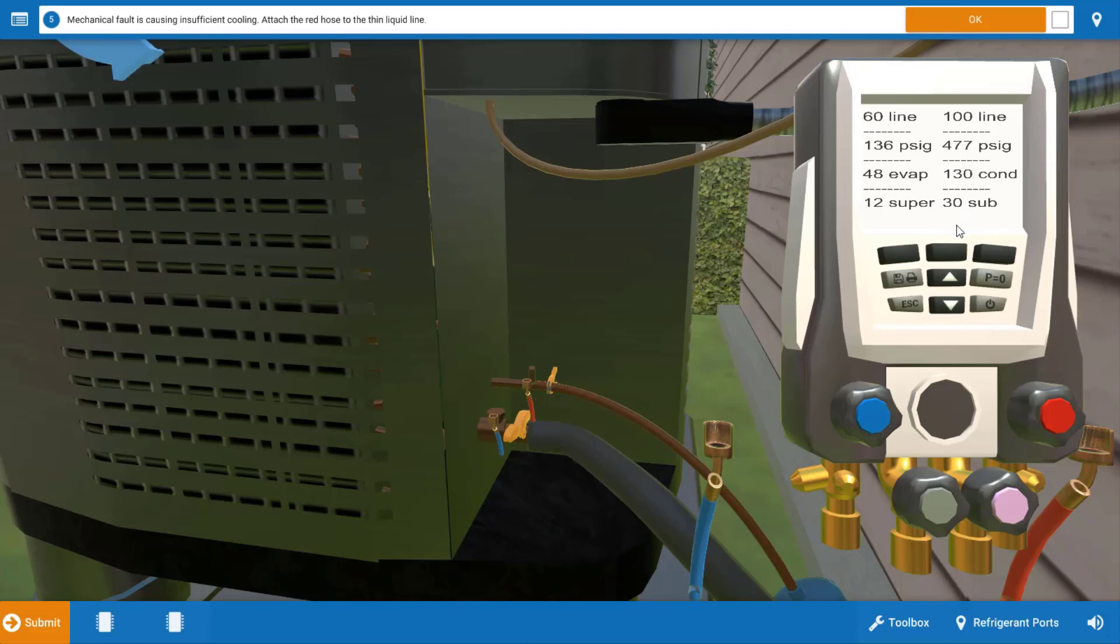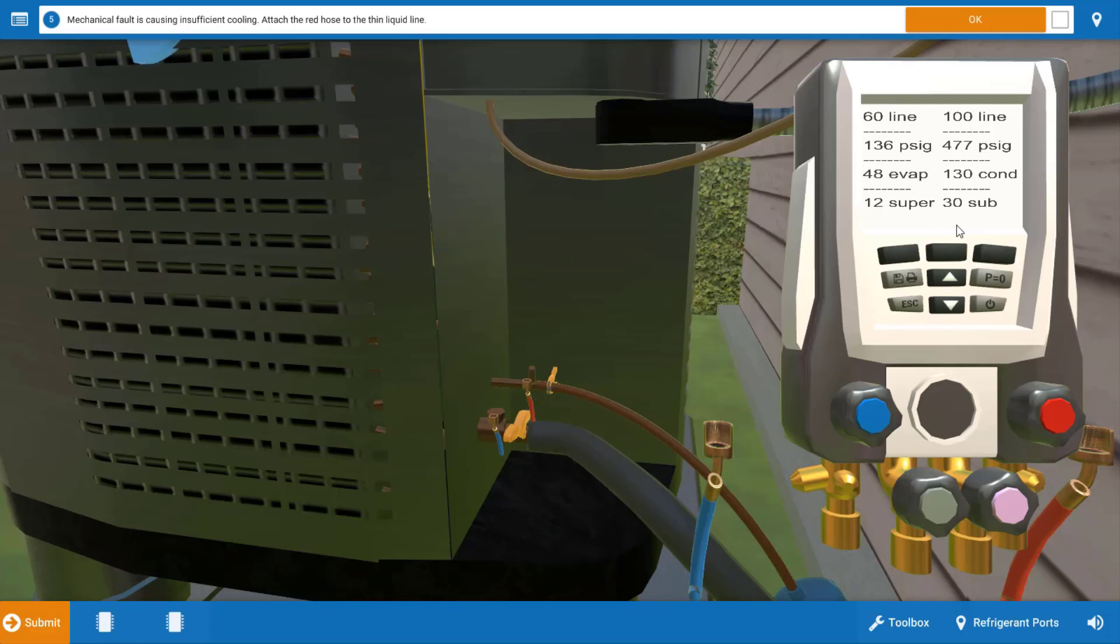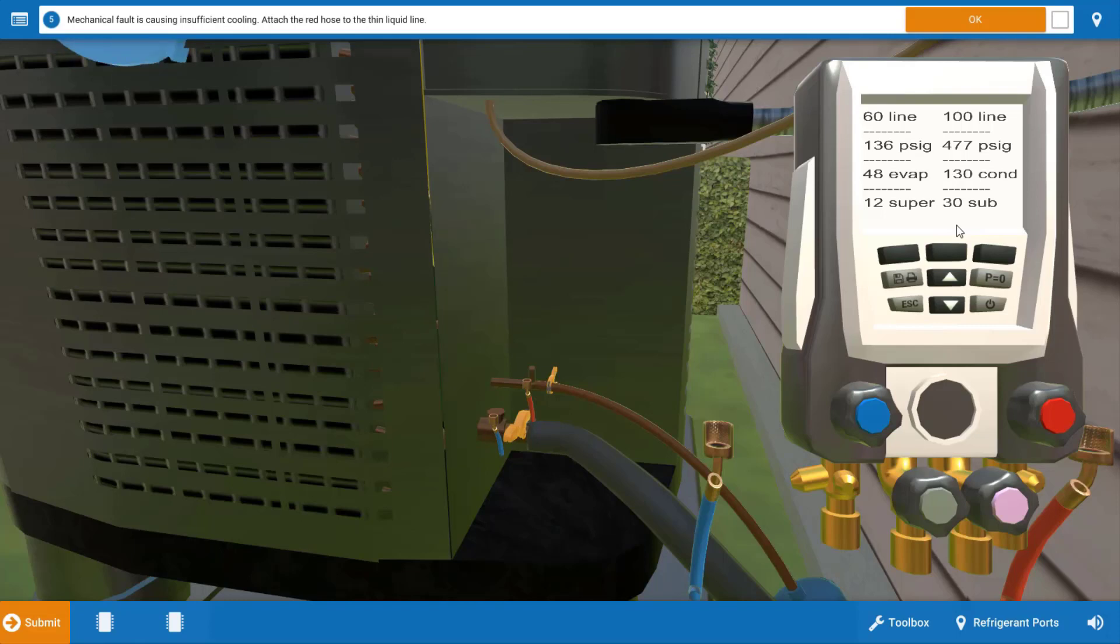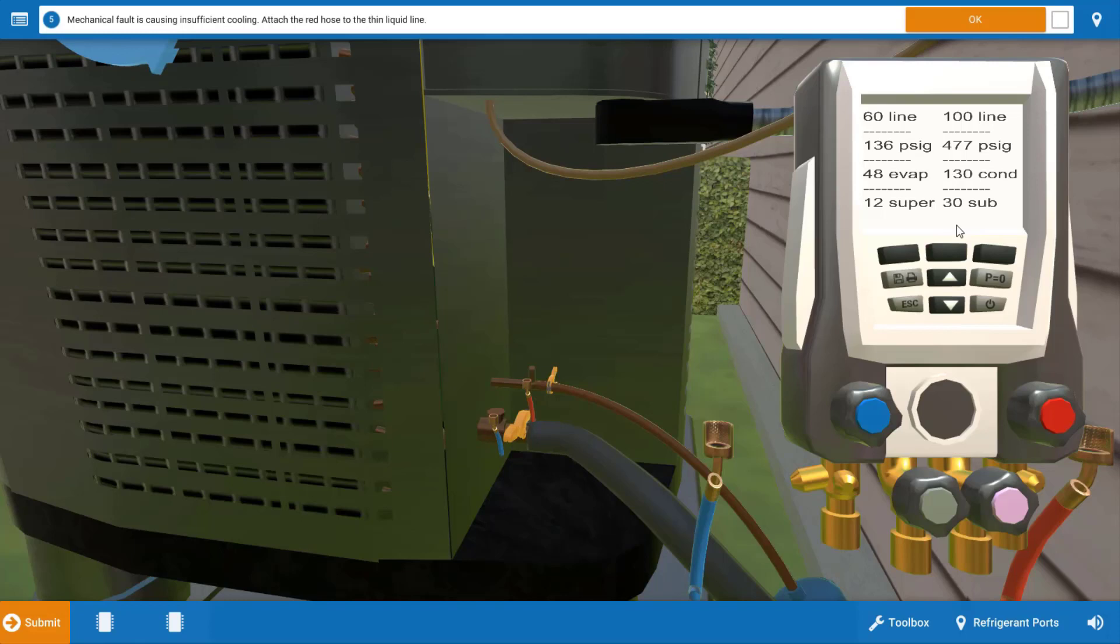Listen, if this had a fixed bore metering device instead of the TXV or thermostatic expansion valve we would use a superheat charging method and an overcharge of refrigerant with a fixed bore metering device would cause the evaporator to be flooded and the superheat would go down and it could even go to zero which would indicate liquid flood back. But again this unit has a thermostatic expansion valve so we do use subcooling here.